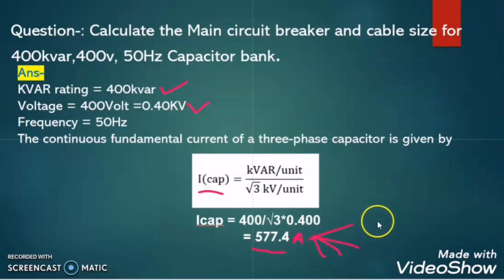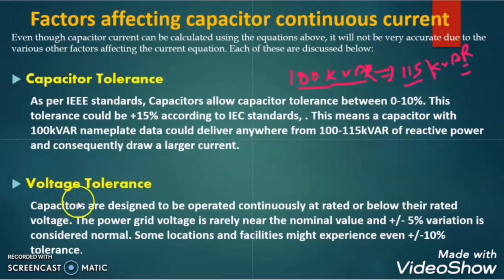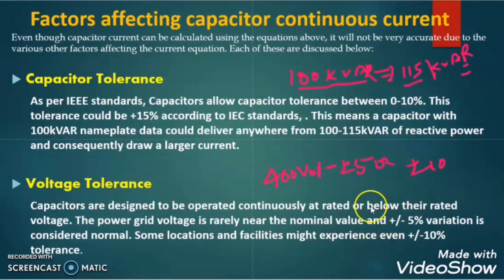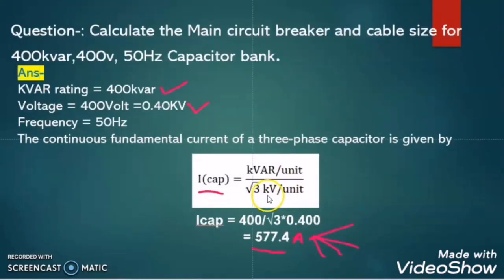Now the voltage tolerance: from the power utility sector, we get the power supply with a voltage of 400V with ±5% or ±10% tolerance. If the voltage changes, then the current of the capacitor will change. Since voltage appears in the formula, if the voltage changes from 400V to 405V or 410V, then the capacitor current value will also change.